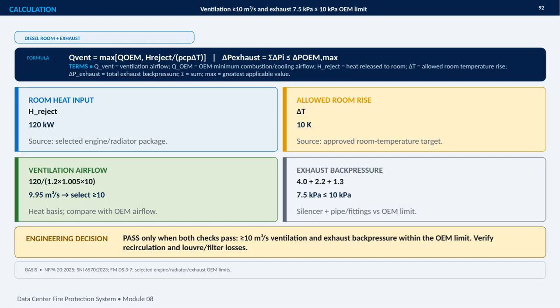This slide shows the calculation used to verify ventilation and exhaust performance for the diesel room. The ventilation requirement is governed by the greater of two values: the OEM minimum airflow, or the airflow needed to remove the heat released into the room. The selected engine and radiator package rejects 120 kilowatts of heat, and the approved room temperature rise is 10 kelvins. Using the stated air properties, the heat balance calculation is 120 divided by 1.2 times 1.005 times 10, which gives approximately 9.95 cubic meters per second. That value is rounded up, so the design must provide at least 10 cubic meters per second, while still being checked against the OEM airflow requirement.